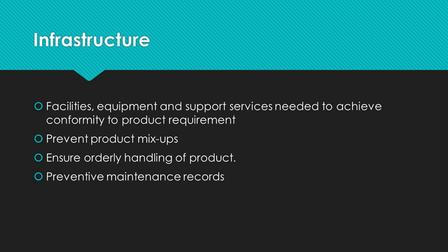Now, once the infrastructure is identified, your job doesn't stop there. You have to identify the maintenance activities and the interval at which they must be performed. And then you better have evidence proving that you actually did those activities. So yes, expect your auditor to look at your preventive maintenance records.